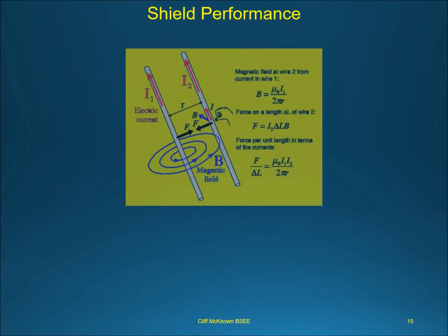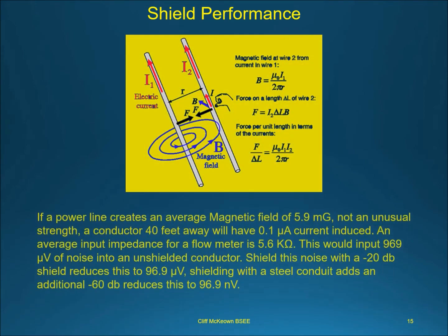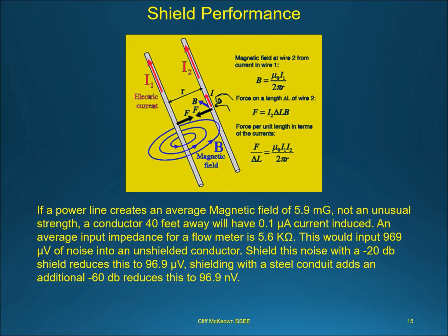The braided shields on our cables offer about minus 20 dB attenuation for EMI, or about 10 to 1. Routing this cable through a steel conduit adds an additional minus 60 dB of attenuation, or roughly a 10,000 to 1 reduction of EMI. If a power line creates an average magnetic field of 5.9 mG — not an unusual strength — a conductor 40 feet away will have 0.1 microamps of current induced. An average input impedance for a flow meter is 5.6 kΩ. This would input 969 microvolts of noise into an unshielded conductor. Shielding with a minus 20 dB shield reduces this to 96.9 microvolts, and adding a steel conduit at an additional minus 60 dB reduces this to 96.9 nanovolts.